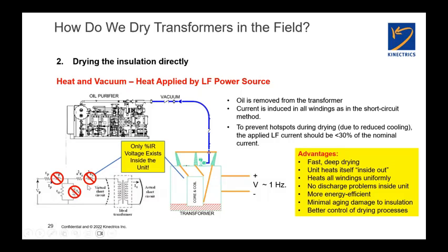And we apply a voltage to one of the windings, which is left open, to get a circulating current going through it. And just like in a heat run or a load loss test, the I squared R losses in the winding manifest themselves as what? As heat, because we're passing current through them. And so we now have a situation where we have vacuum and heat constantly being produced inside the winding at the same time, which is the optimum situation, heat and vacuum simultaneously. The analogy that I like to give folks is it's like cooking a chicken at home.